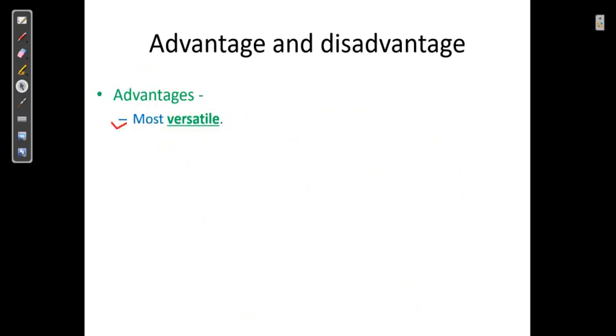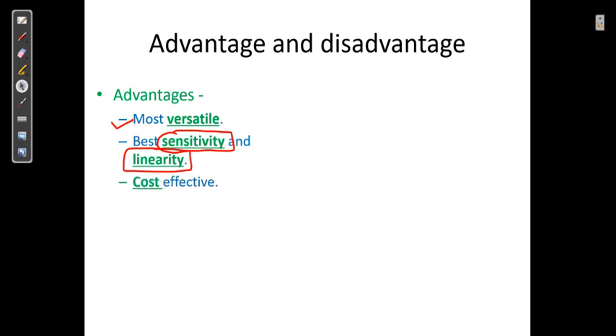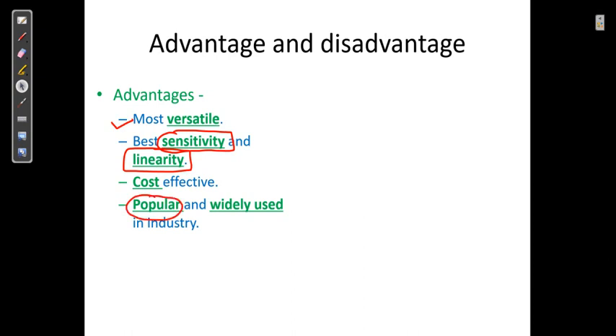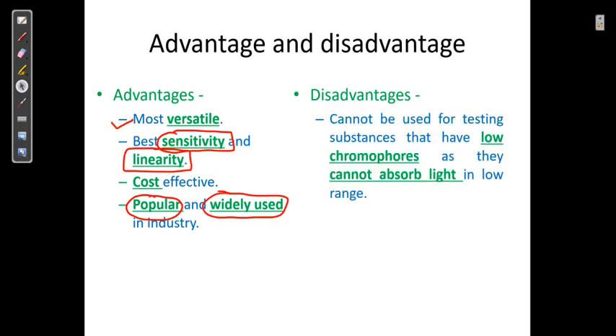The advantages of the UV detector: it is the most versatile, offering both qualitative and quantitative analysis. It has high sensitivity and good linearity, and is cost-effective and popular. The disadvantage is that it cannot be used for substances that have a low chromophore.